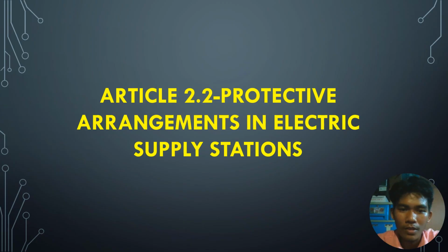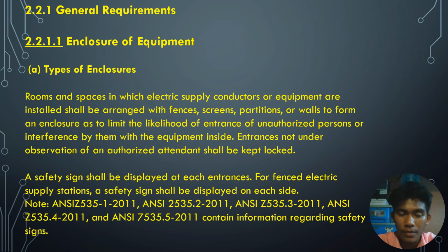Let's start with Article 2.2. Protective arrangement in electric supply station. General requirements. Enclosure of equipment. Types of enclosure. Rooms and spaces in which electrical supply conductors or equipment are installed shall be arranged with fences, screens, partitions, or walls to form an enclosure as to limit the likelihood of entrance of unauthorized person or interference by them with the equipment inside.